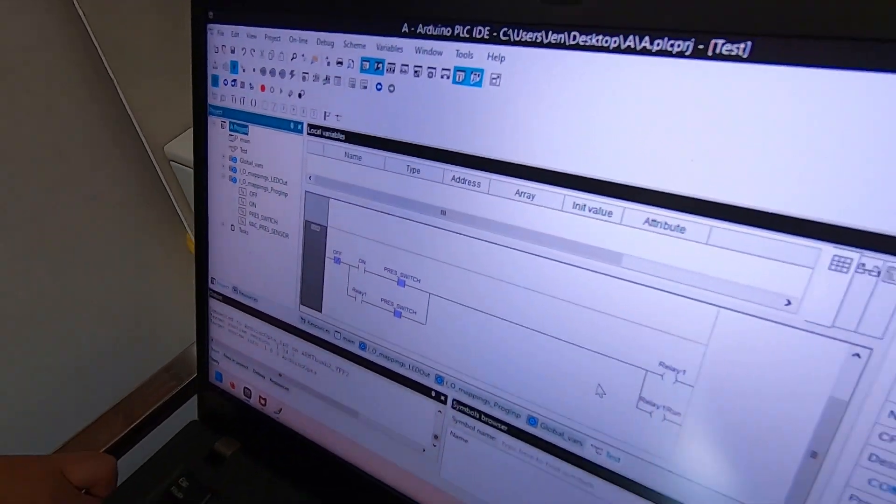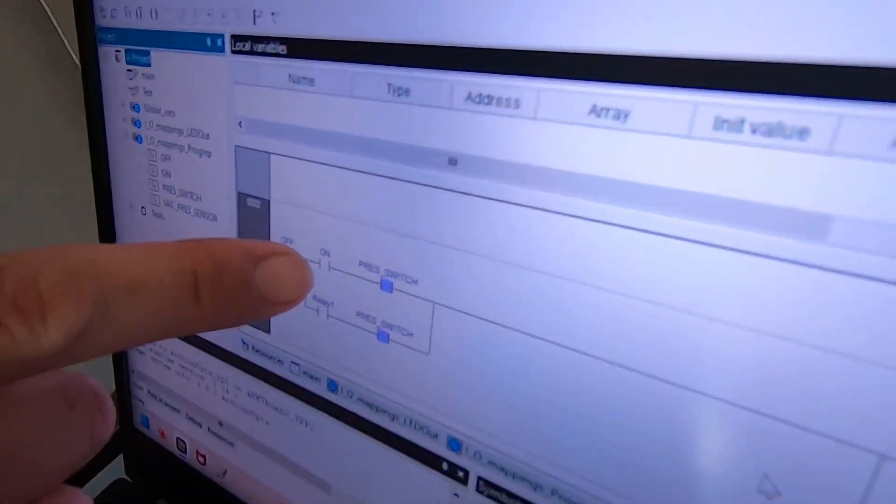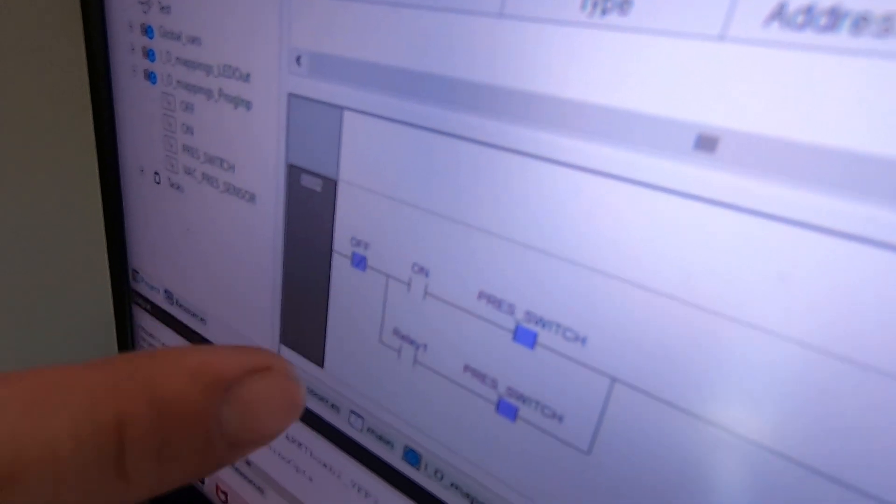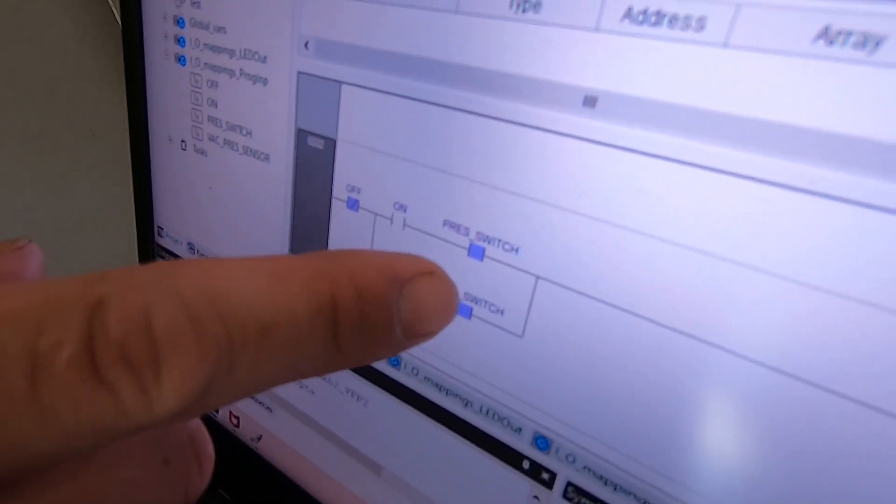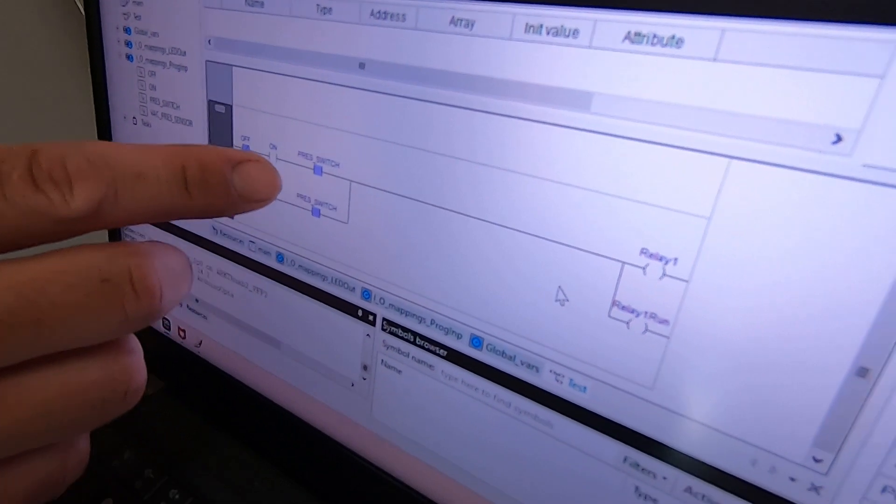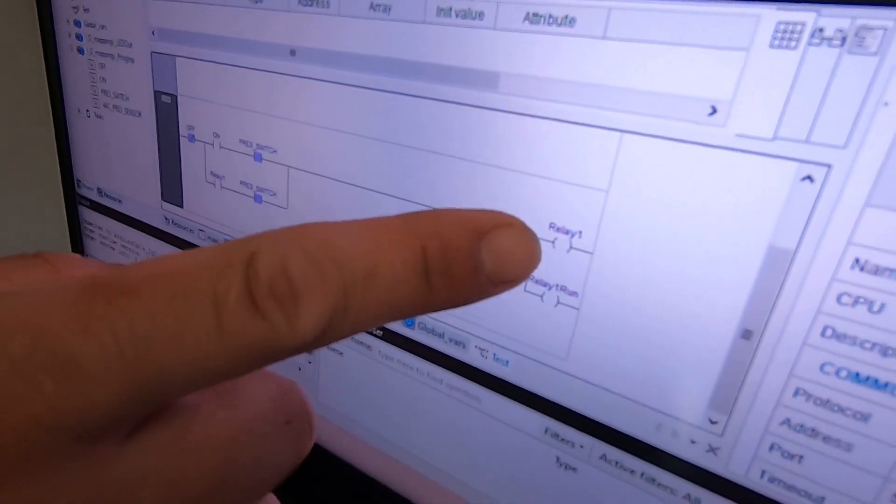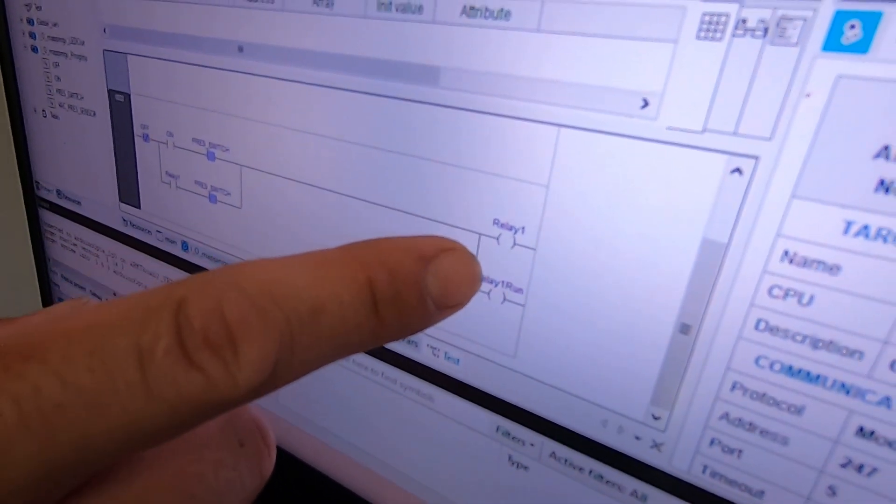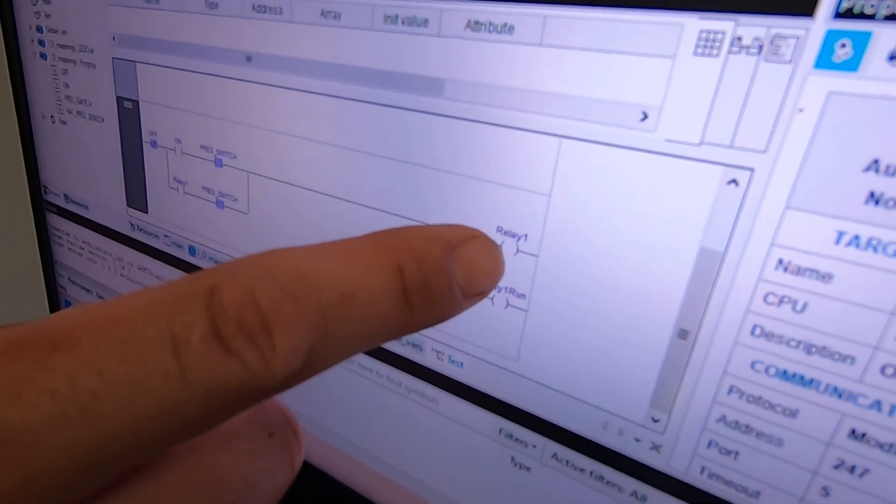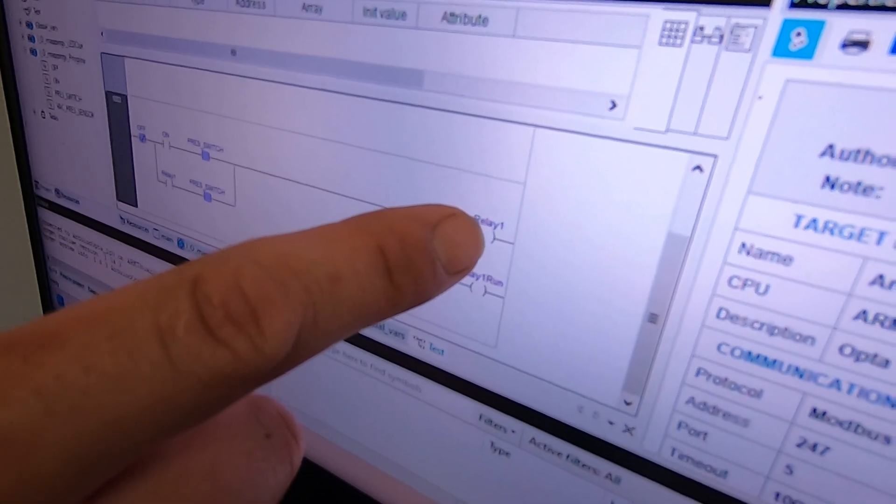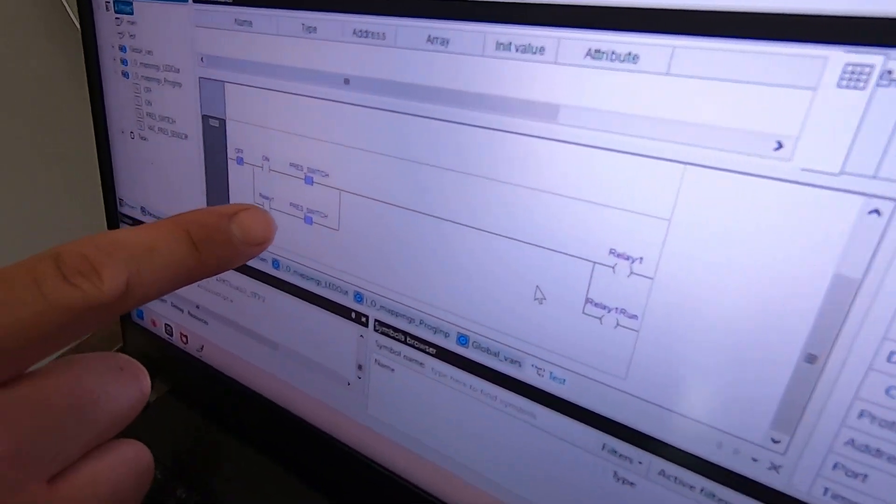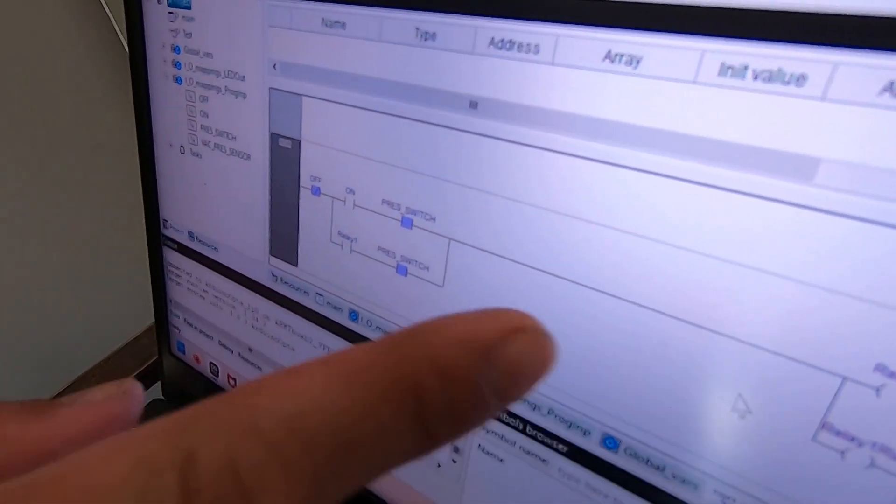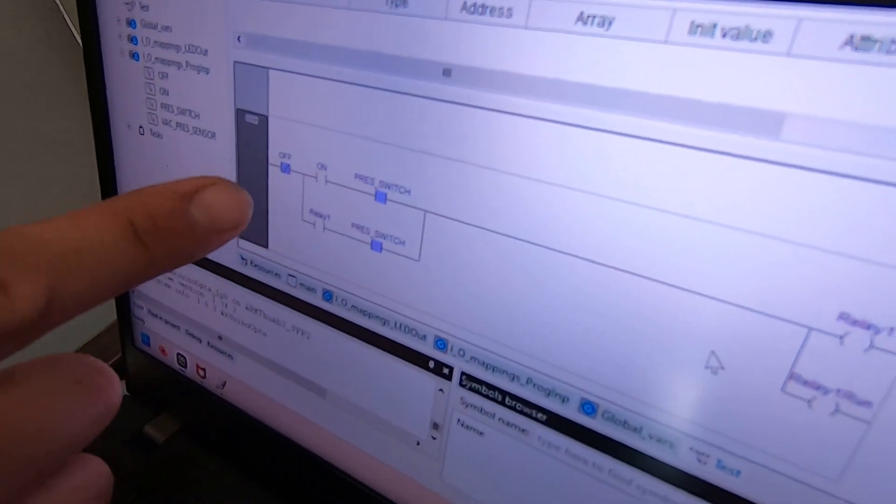Next thing I have is the on switch which is going to be our input two and then I have the pressure switch which is normally closed and then it will open at 175 PSI. This relay activates that contactor for the motor and also have an auxiliary contact on that relay where when that is on this will be on.